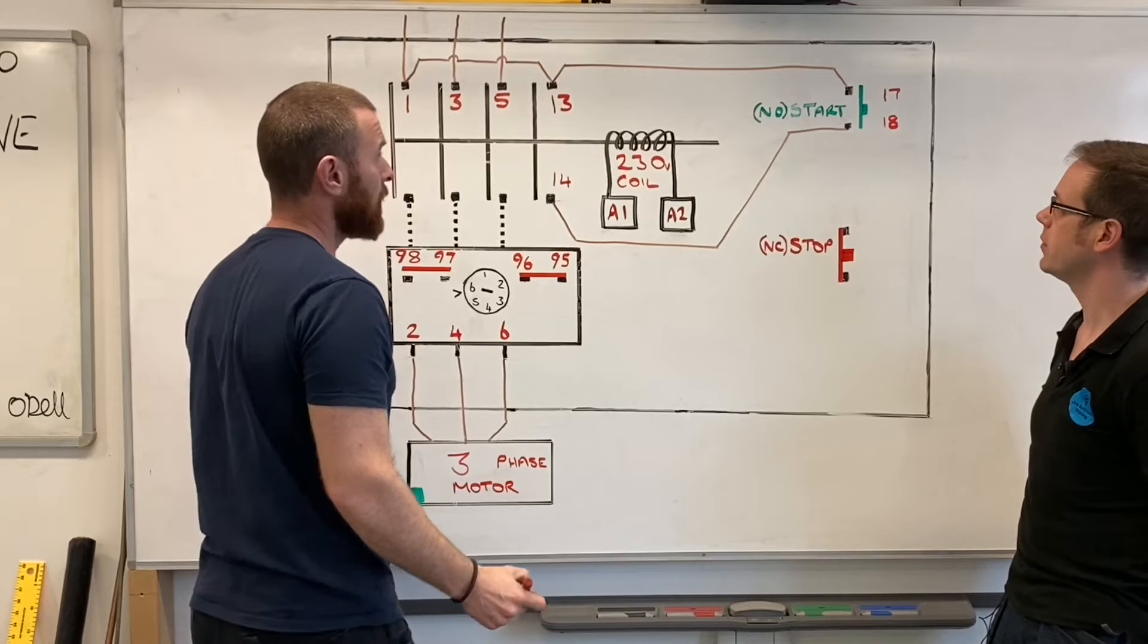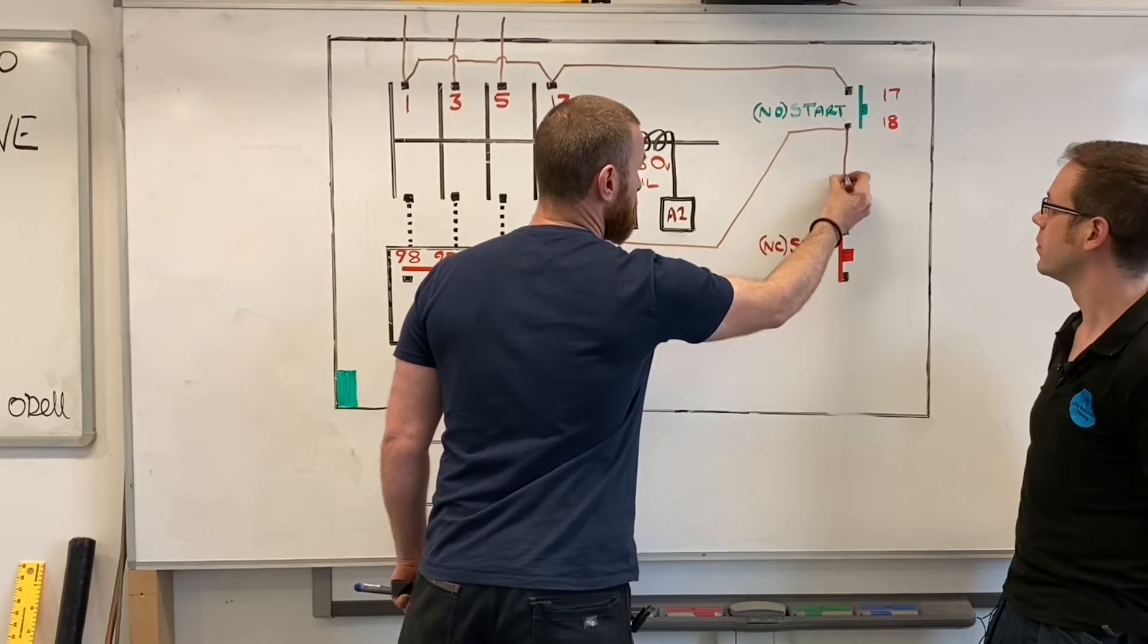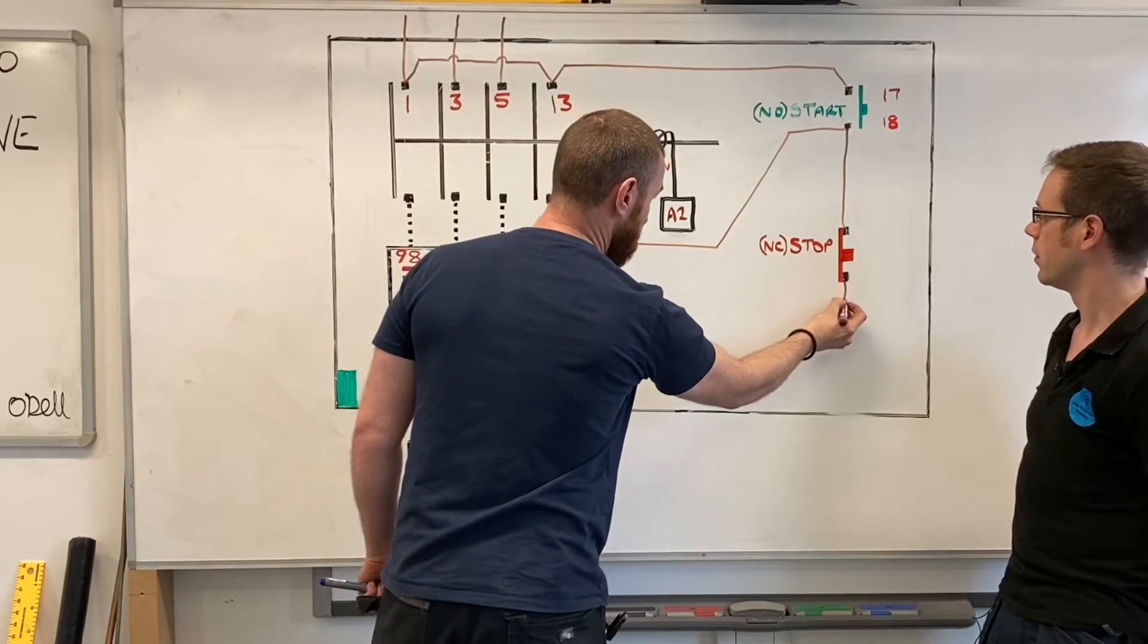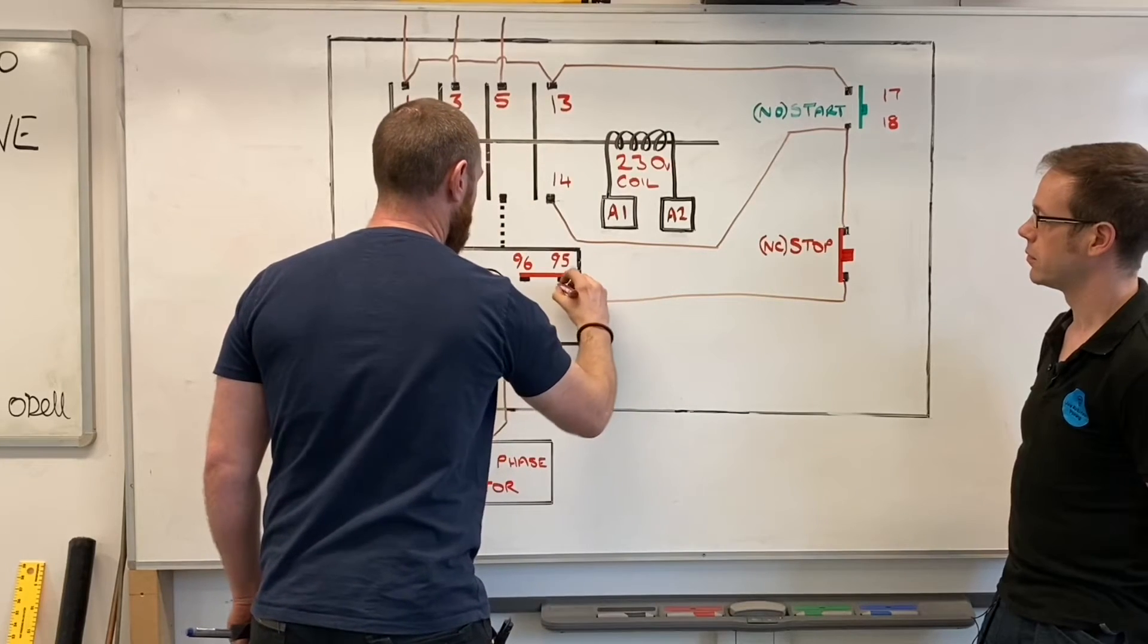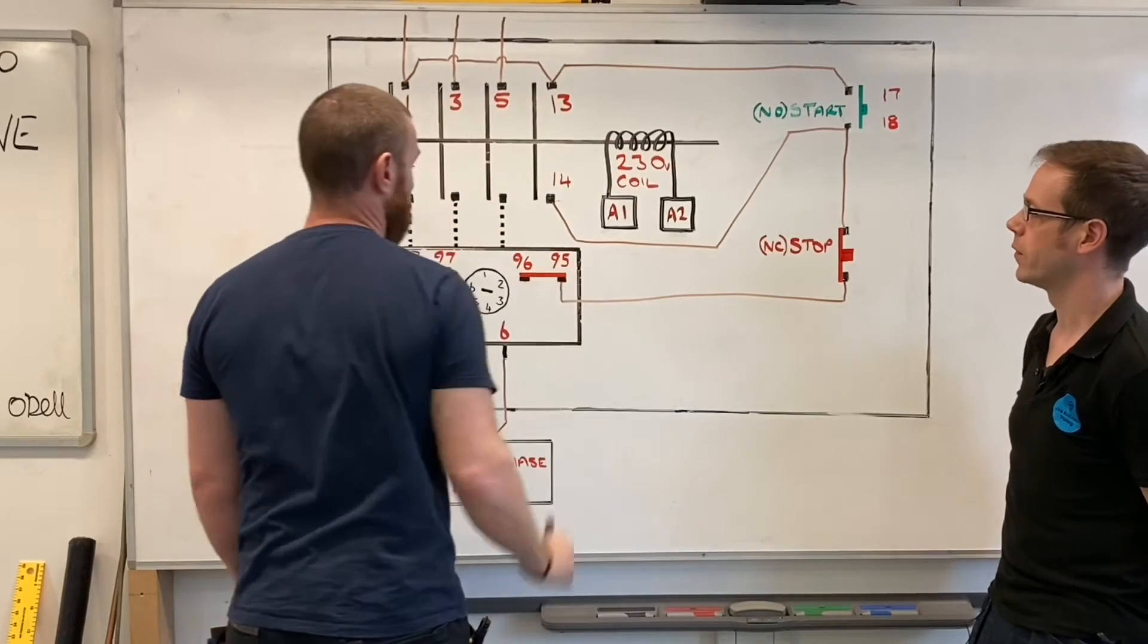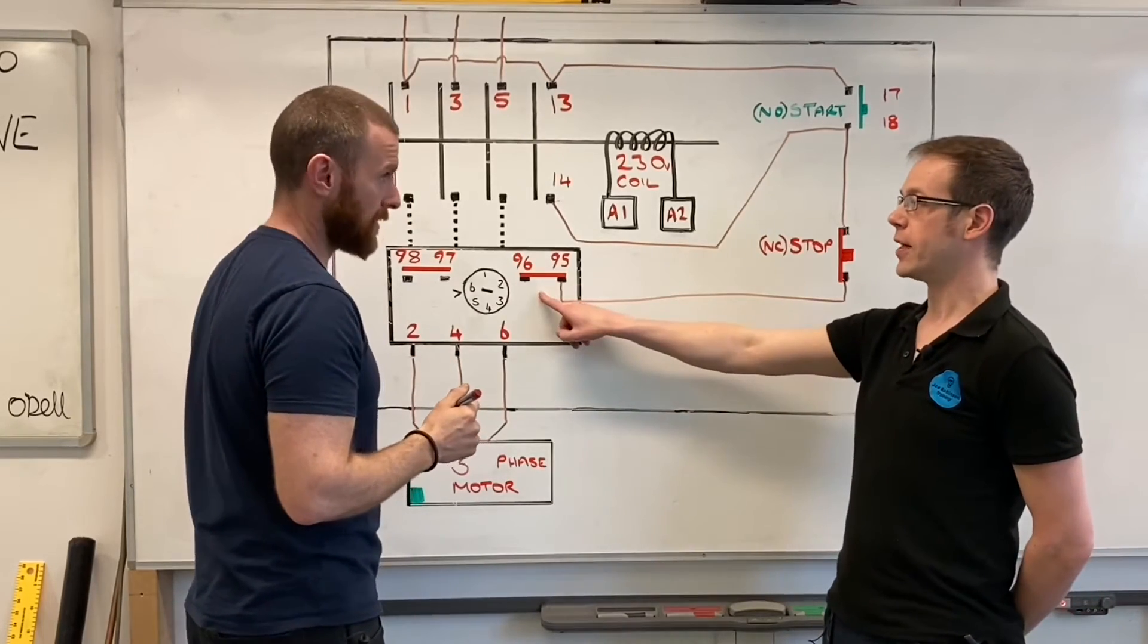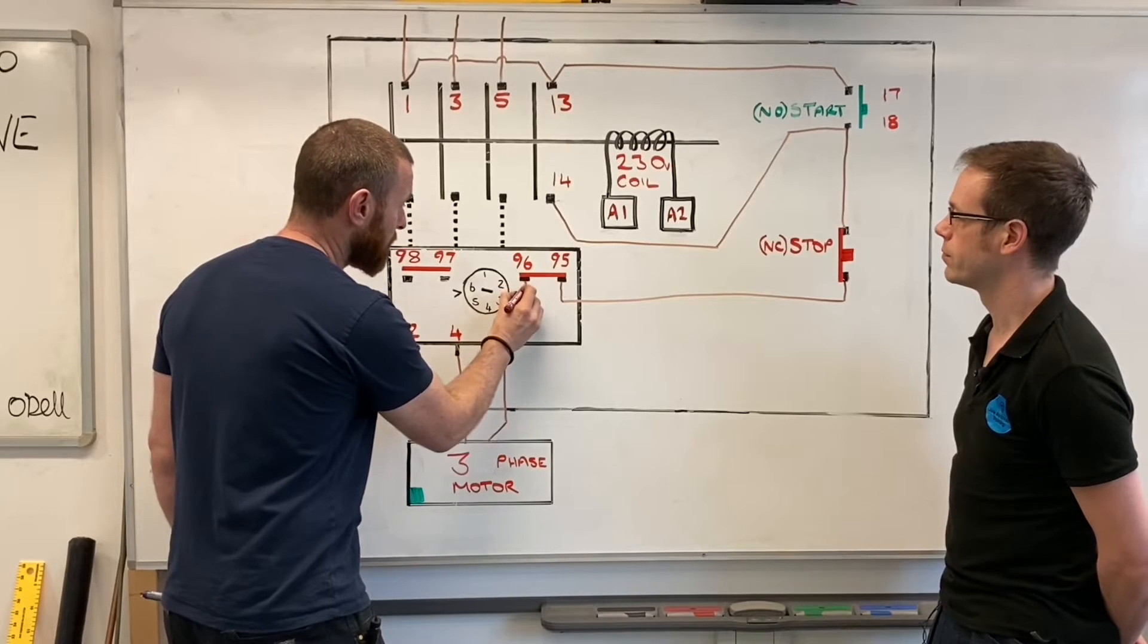Everything looks pretty much the same as how it was before. We need to take down from number 18 down to the stop button, and then from the stop button all the way across to the normally closed terminations of 95 and 96. So this is our overload contact.